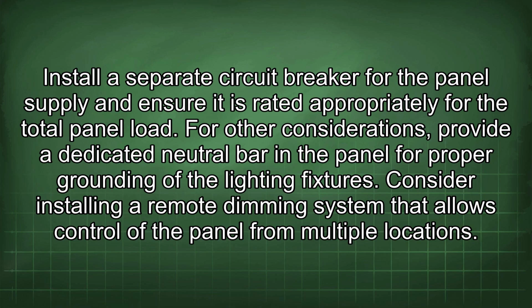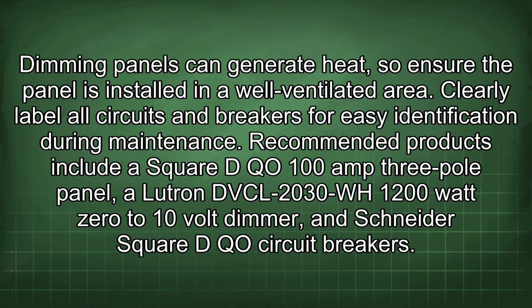For other considerations, provide a dedicated neutral bar in the panel for proper grounding of the lighting fixtures. Consider installing a remote dimming system that allows control of the panel from multiple locations. Dimming panels can generate heat, so ensure the panel is installed in a well-ventilated area. Clearly label all circuits and breakers for easy identification during maintenance.